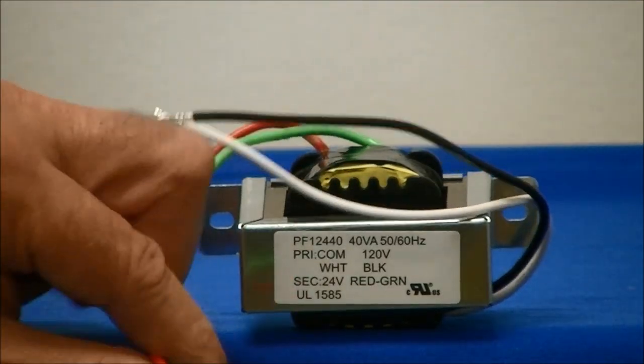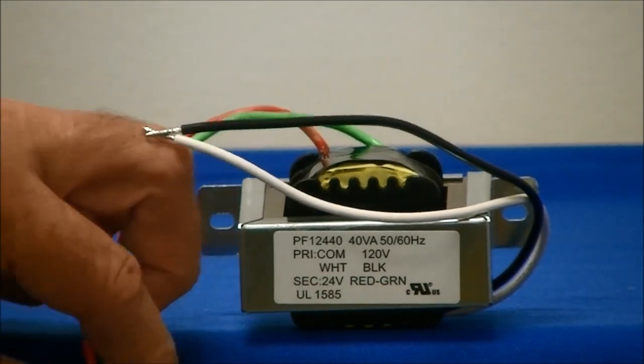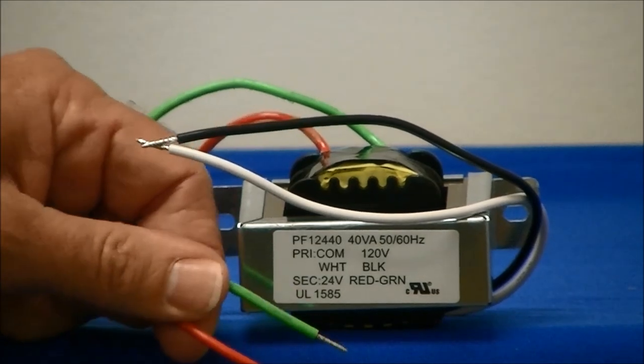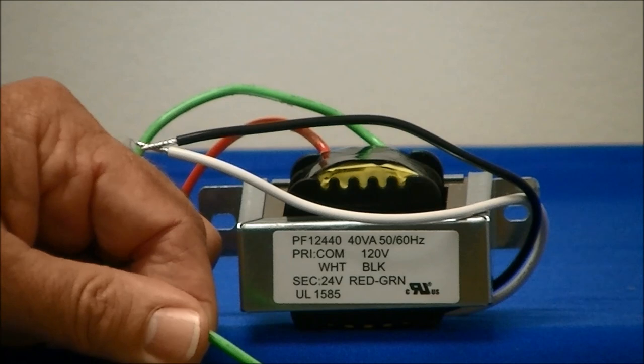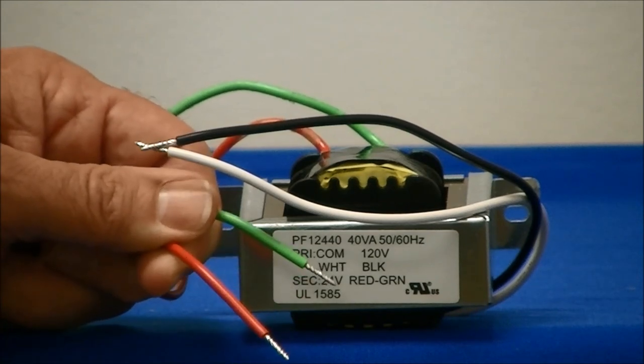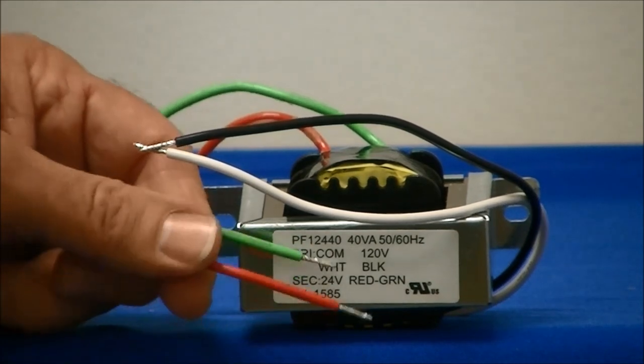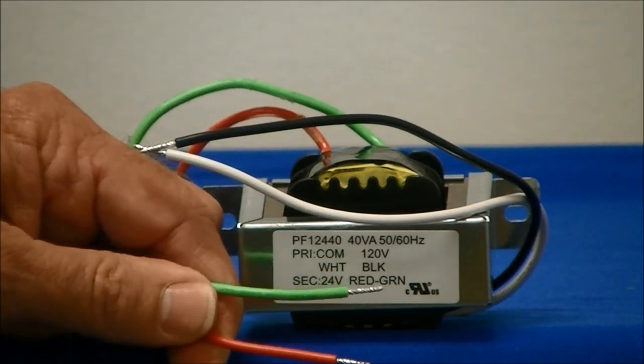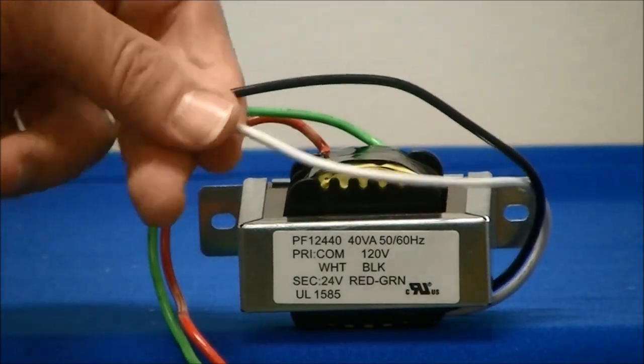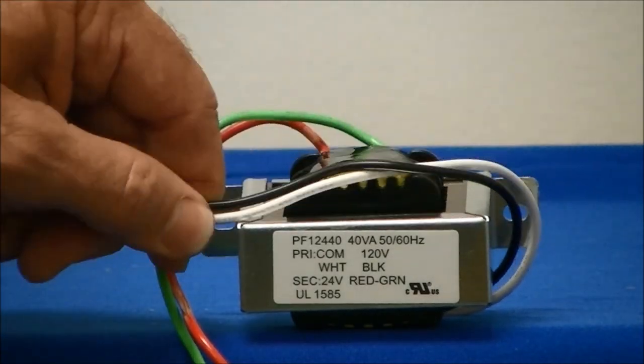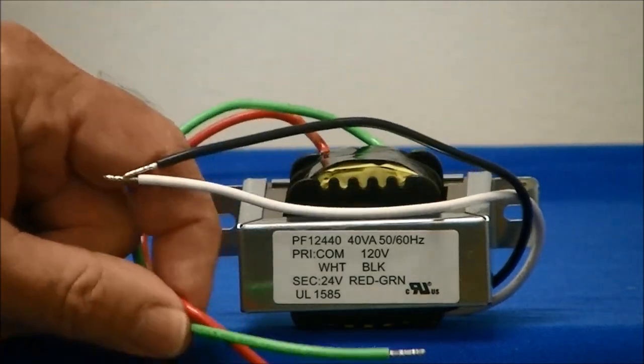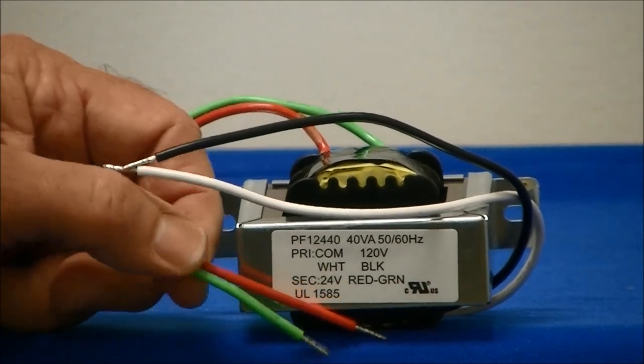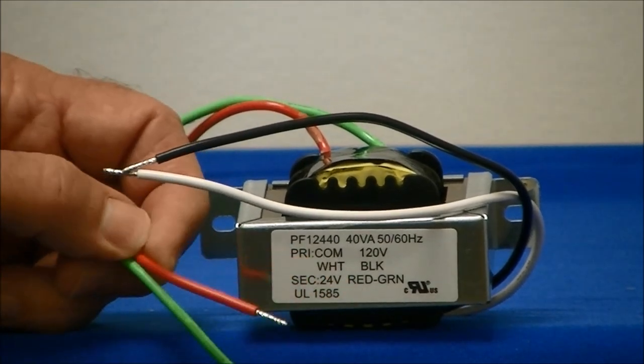The secondary coil, in this case is 24 volts, and the secondary coil then provides 24 volts to the appliances, to the thermostat, to the contactor, to different products that need to be sourced by that low voltage. So the primary is the power coming out of the main power source, out of the wall. The secondary is the power then going to the additional apparatus that you attach.